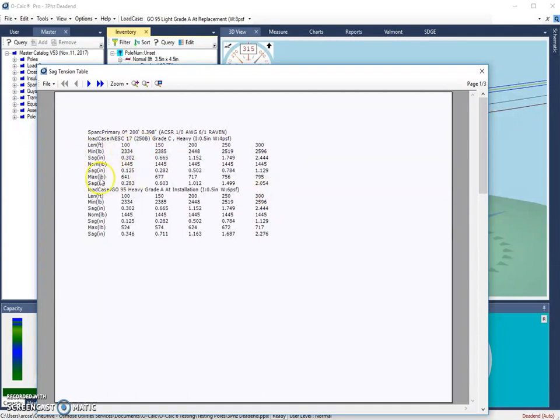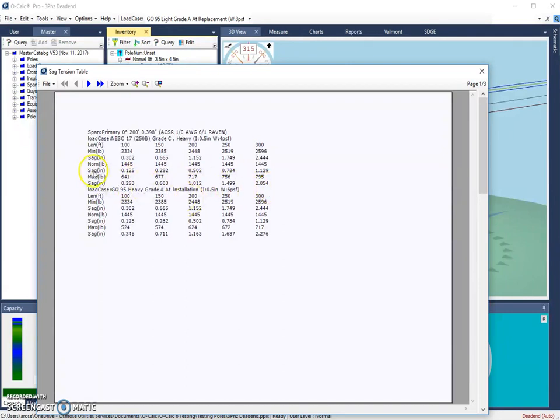So if we go down to this section here, we can see with a maximum temperature what our tension would be and our amount of sag also indicated. Now you get the same information for a different load case shown down here. So you can see what that load case is doing to those values.